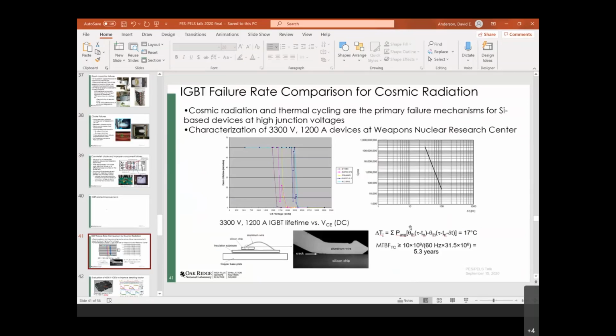No, we don't believe they were. We think they were primarily associated with overvoltage conditions across the IGBTs, because that's what all the data and measurements indicated. When we addressed that with a snubber, the failure rate went down by a couple orders of magnitude. So basically more overvoltage-related challenges.